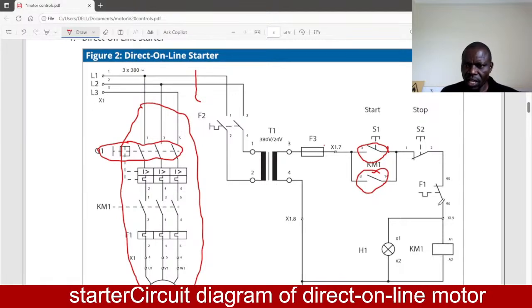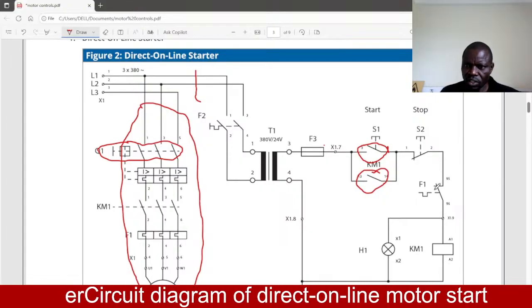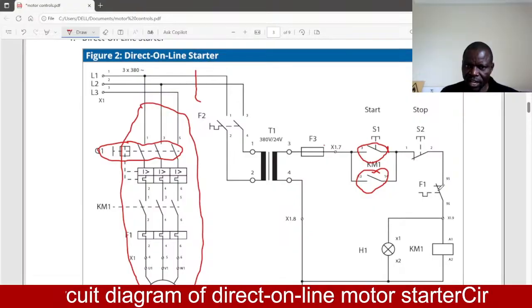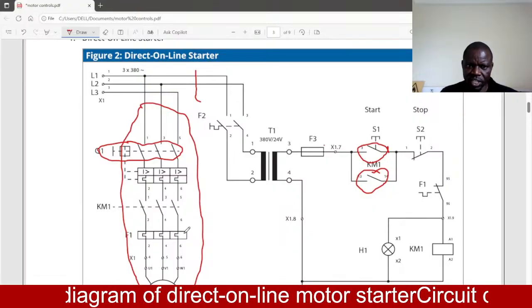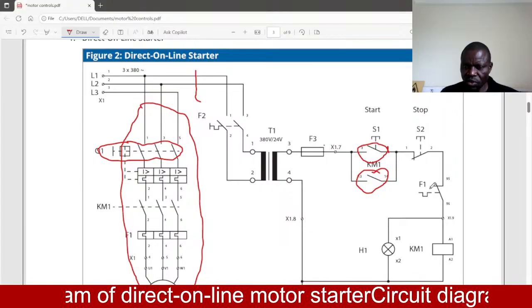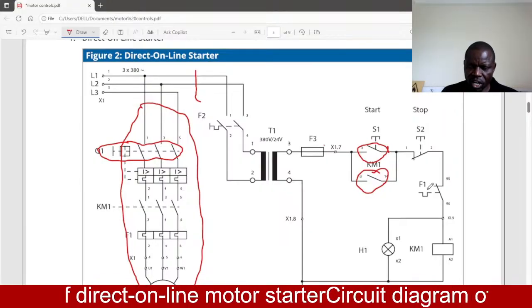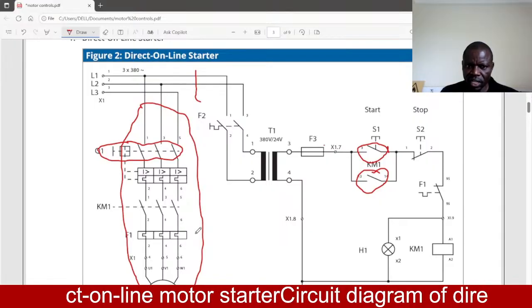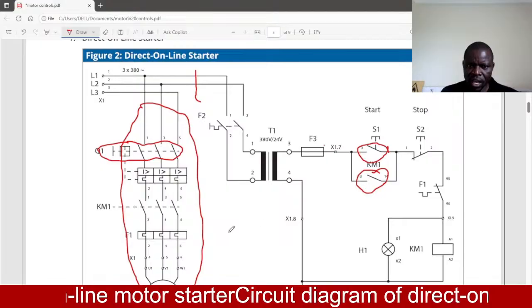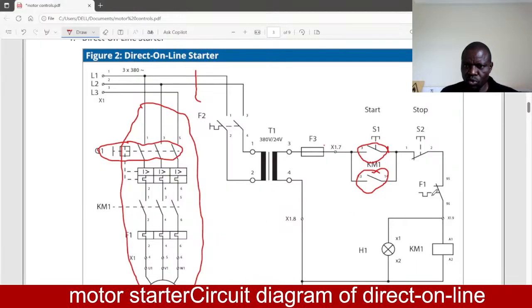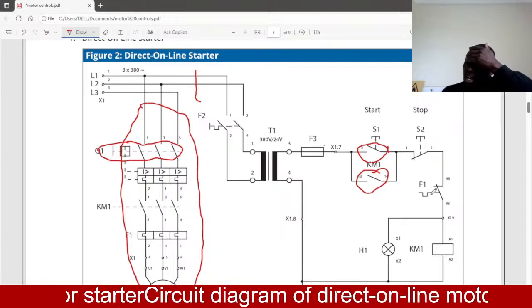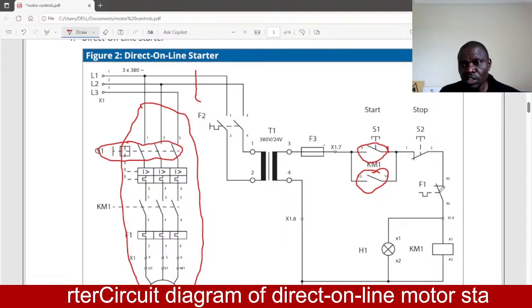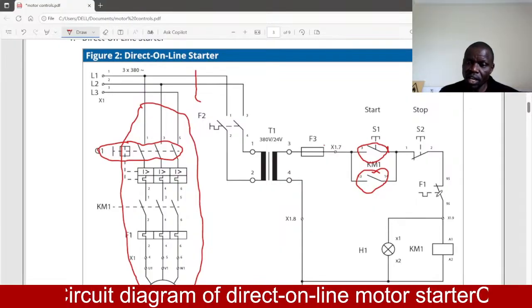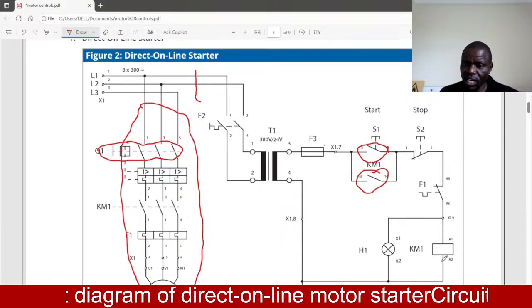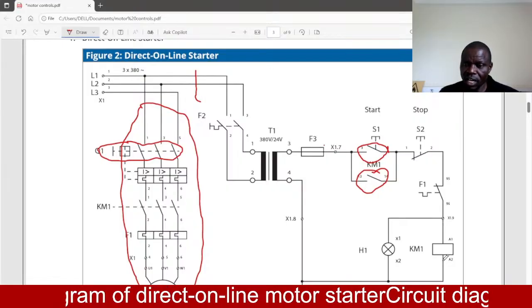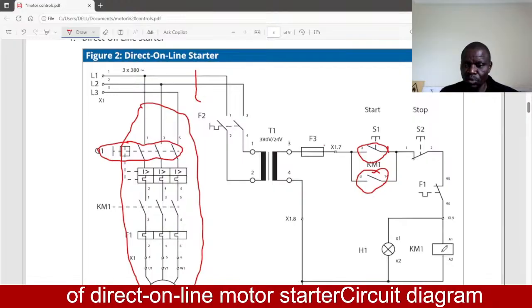And this other one here is our overload. This overload contact switch here is attached to the overload relay, and it operates in conjunction with it. When current flowing to the motor is exceeded, the overload relay will heat up, and the overload relay has a mechanism of a bimetallic strip. This bimetallic strip will bend, and by so bending it will trip this contact here and it will open, hence de-energizing the contactor coil and the motor. The circuit will be switched off.